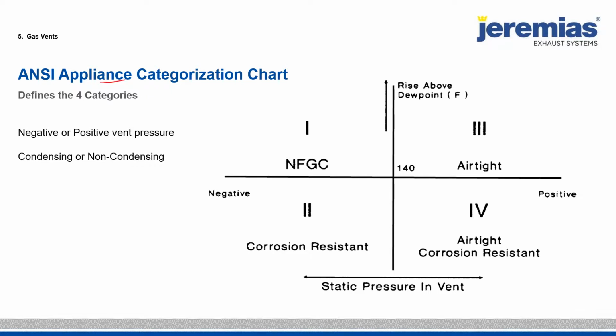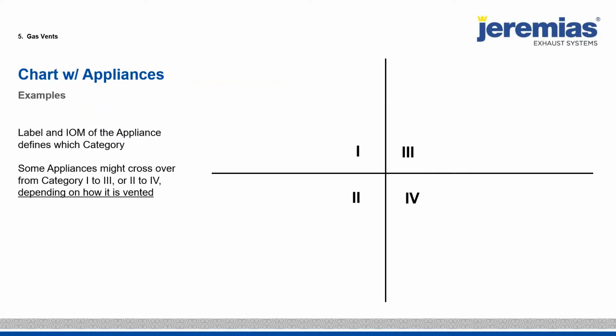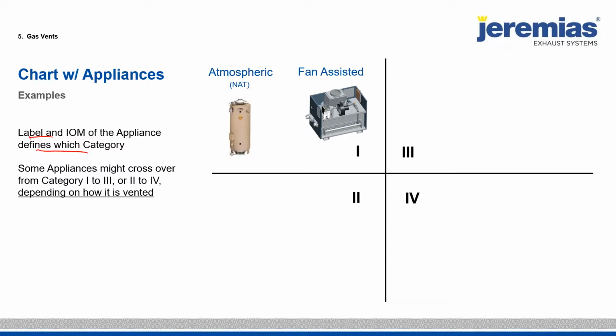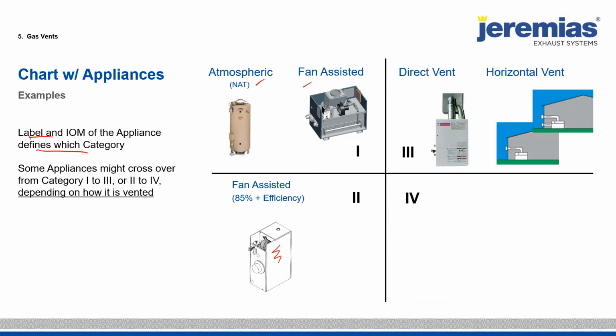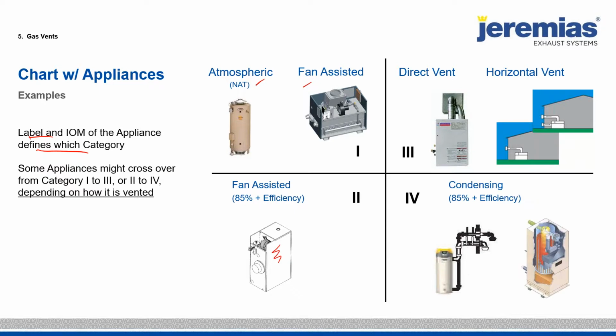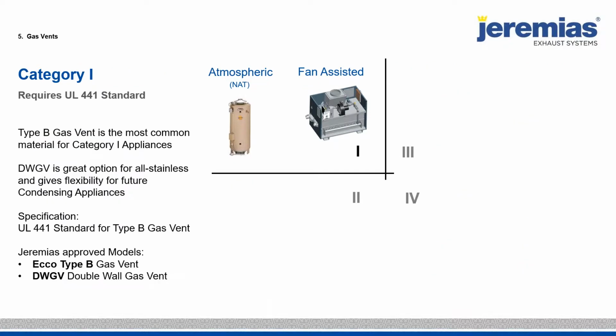Now, I do want to talk about these ANSI venting categories. Every appliance is stamped and shows what category it is if it's a natural gas only appliance. So again, the IOM or the label defines the category, but category 1 appliances would be anything that's atmospheric or maybe fan assisted. It's basically non-condensing, and also requires a negative vent pressure. Category 2 is sort of phased out because this is what the category 4 appliances use to define how to common vent direct vent systems. Category 3 would be something like a tankless water heater. It's not condensing, but it has a positive vent pressure. You're pushing the flue gases through the pipe. And then category 4 would be the entirely condensing appliances that may or may not be able to use plastic PVC systems.